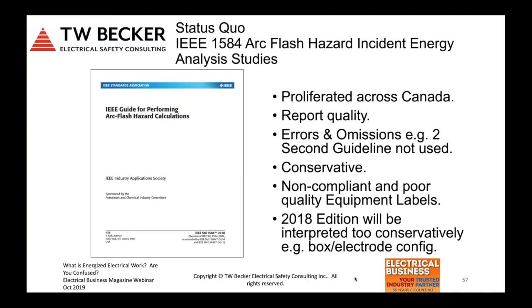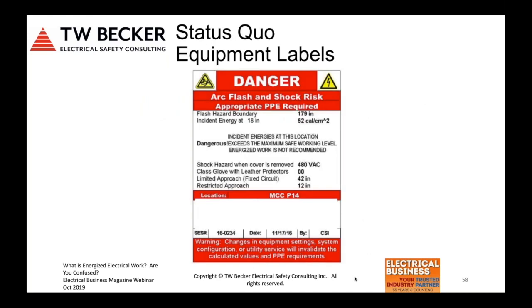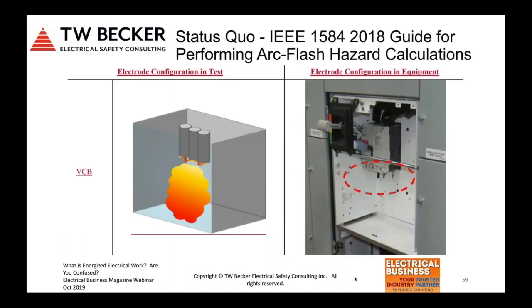So I encourage you, if you're the owner of the electrical equipment, that you review your current studies, you review your labeling, and then going forward, as I'm going to highlight, there's been significant changes to the formulas that you have to make sure are reasonably determined and not conservatively determined, or it can have an impact on incident energy going up potentially 200%. So there's an example of what I call a non-compliant label. It has 52 calories. It says that dangerous, exceeds the max safe working level, and work is not recommended. So again, it's putting policy on a label that shouldn't be there. Again, lots of non-compliant labels out there. I encourage you to review your labels going forward.